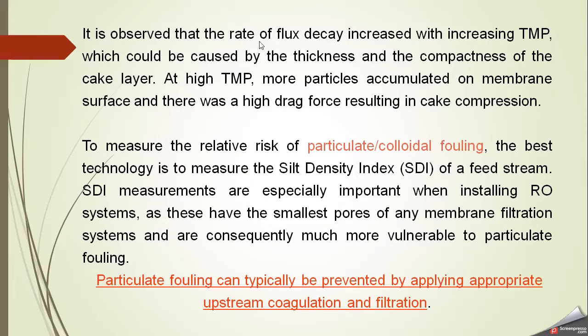The rate of flux decay increases with increasing transmembrane pressure (TMP). As pressure increases, more colloidal particles deposit on the cake, further decreasing flux and increasing the thickness and compactness of the cake layer. The measure of the relative risk of particulate and colloidal fouling is the SDI test — the silt density index of the feed stream. We measure the SDI of the feed stream to decide whether the water needs more pre-treatment. Ideally, the SDI value should be less than 3.